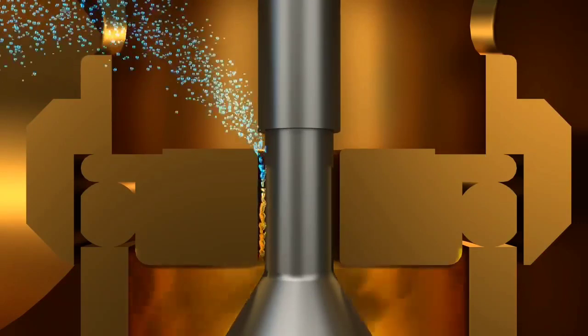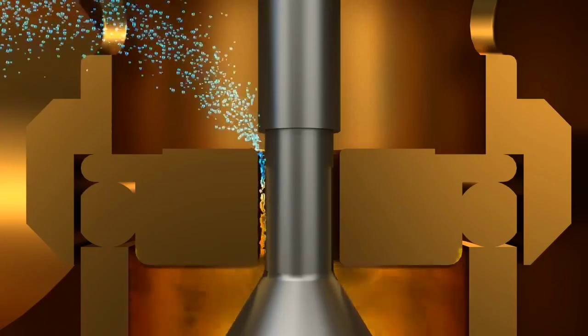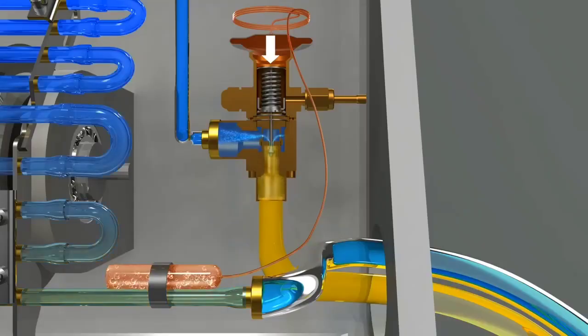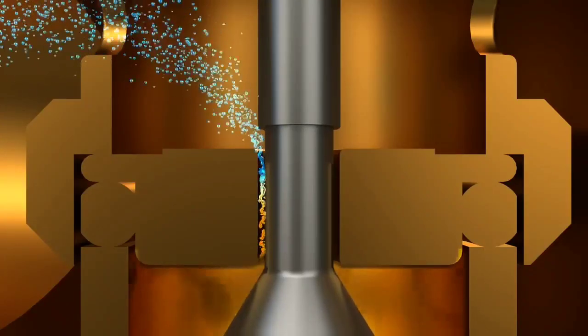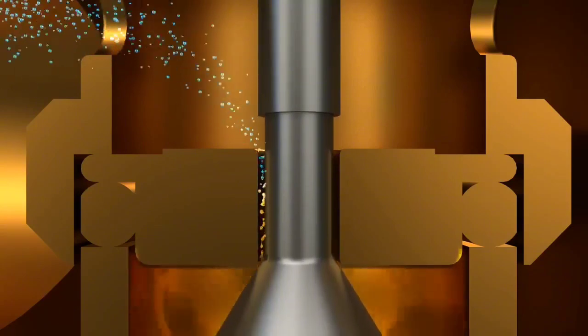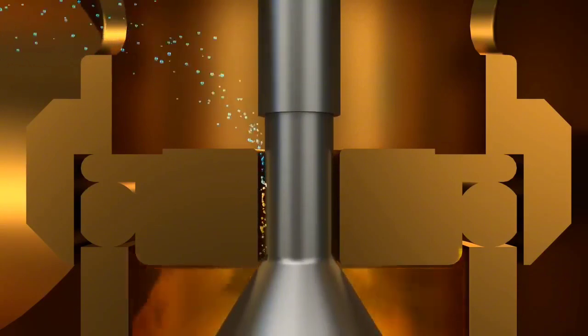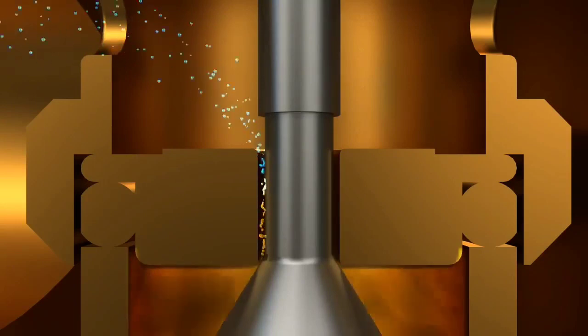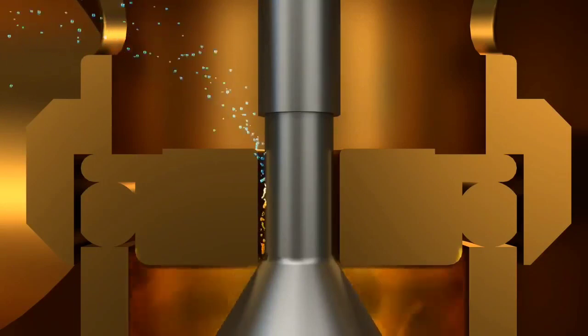When the amount of refrigerant going into evaporator surges, cooling emission surges too. When the temperature at the exit of an evaporator drops, gas pressure drops and the amount of refrigerant going into evaporator in turn drops too. Applying the above principle, an air conditioner controls the amount of refrigerant injected into an evaporator to prevent overcooling.